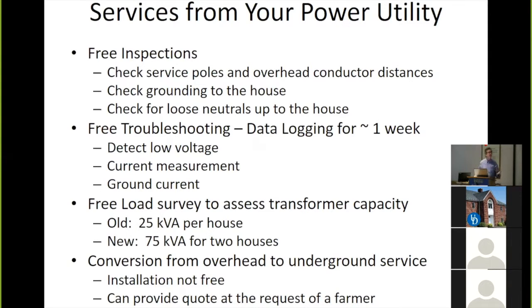For example, low voltage. One of the things AC motors don't like is low voltage. When the voltage goes down and it still has to meet that load demand, electric current goes up. And as more current flows, more heat happens, which makes motors hot. So making sure your utility is giving you proper line voltage is something they'll do for free, and something you should have checked once in a while, even if it's every few years. Again, they'll do it for free.